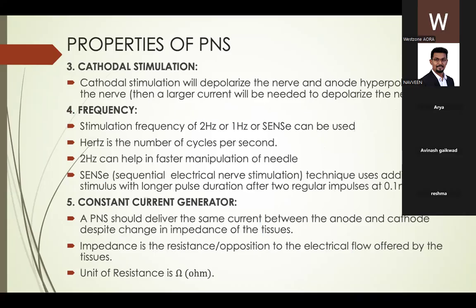Coming to the frequency, the stimulation frequency can be either 1 hertz, 2 hertz, or SENSe. Hertz is the number of cycles per second. 2 hertz can help in faster manipulation of the needle. The SENSe mode is a sequential electrical nerve stimulation technique which uses an additional stimulus with a longer pulse duration after 2 regular impulses at 0.1 milliseconds. So this becomes like a 3 hertz.